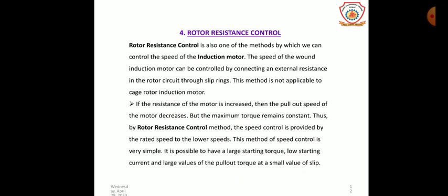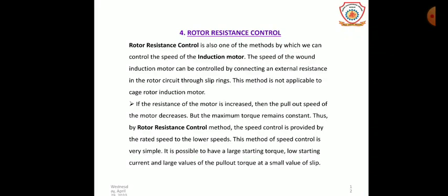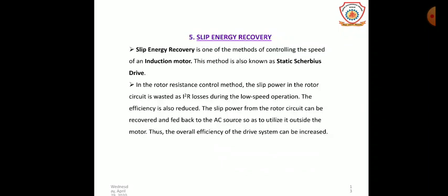The rotor resistance control method is an important method of controlling the speed of an induction motor. The speed of a wound induction motor can be controlled by connecting an external resistance in the rotor circuit. The larger the value of resistance, the larger the slip at which maximum torque occurs. This method provides speed control from rated speed down to lower speeds. It is a very simple method, with examples including fan and pump drives.